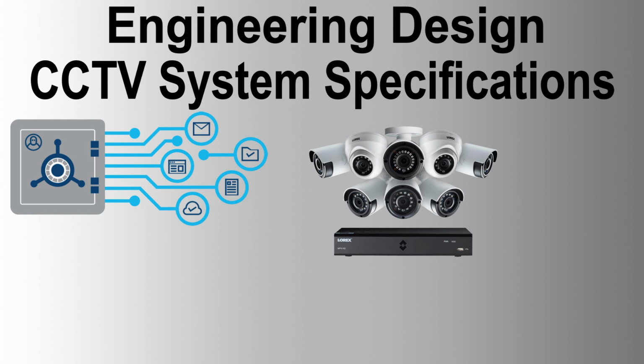Testing shall demonstrate system compliance and performance in accordance with project documents and specifications. The FAT shall include but not be limited to the following: visual checks, earthing isolation and continuity measurements, diagnostic features, hardware checks, functional tests, input-output video signals and reporting tests, communications interfaces test, system response tests with all cameras simulated at worst loading conditions, RFI and EMI testing.